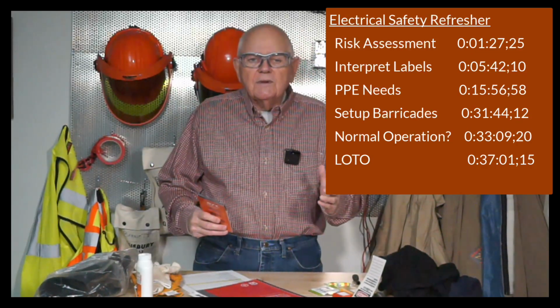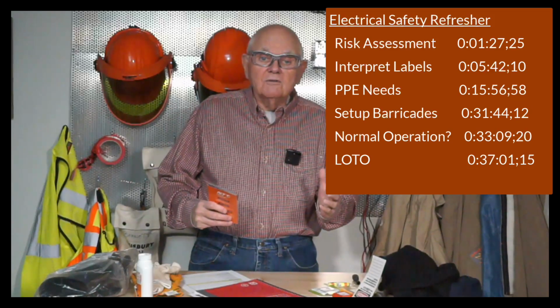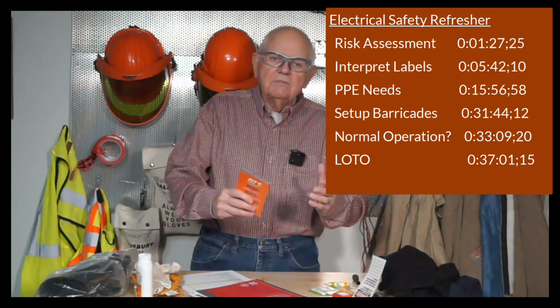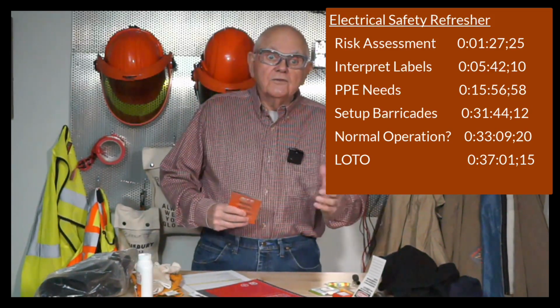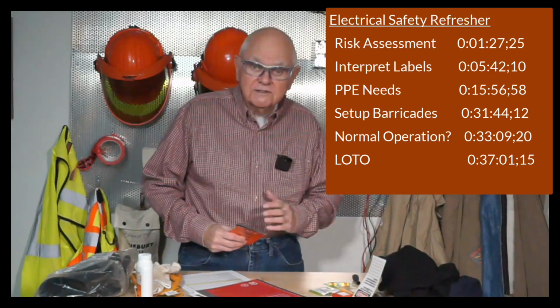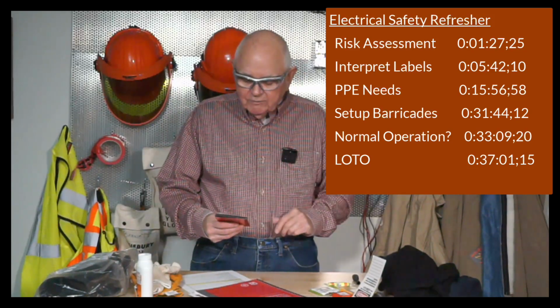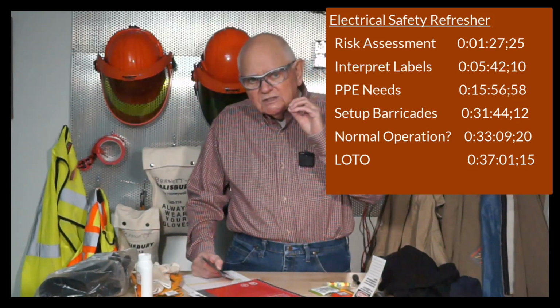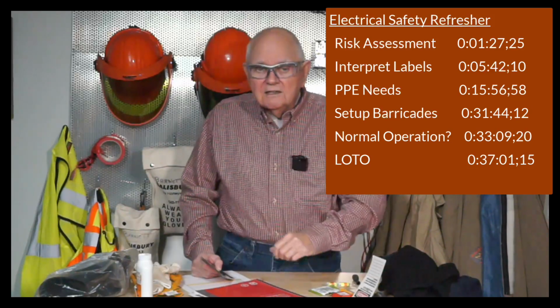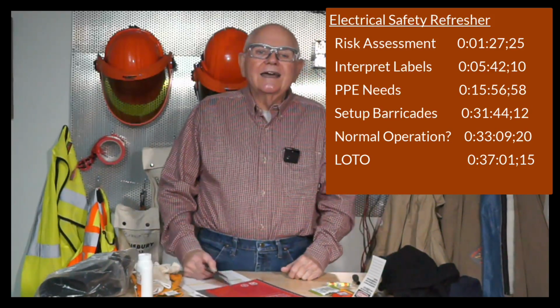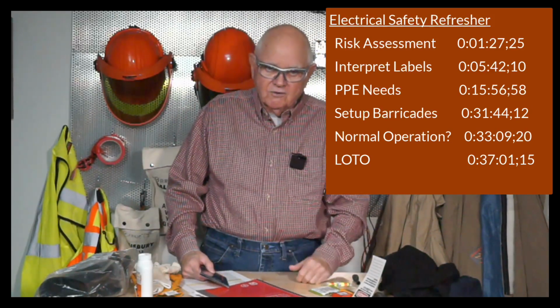The second thing we probably want to do out there in the field, once we do our risk assessment, is gather up our PPE to go to work. So we're going to go through the selection of our PPE as well as our test equipment. The third topic that we're going to go over is we want to make sure that the equipment is safe to operate. So we're going to talk about verifying that equipment is suitable for normal operation.